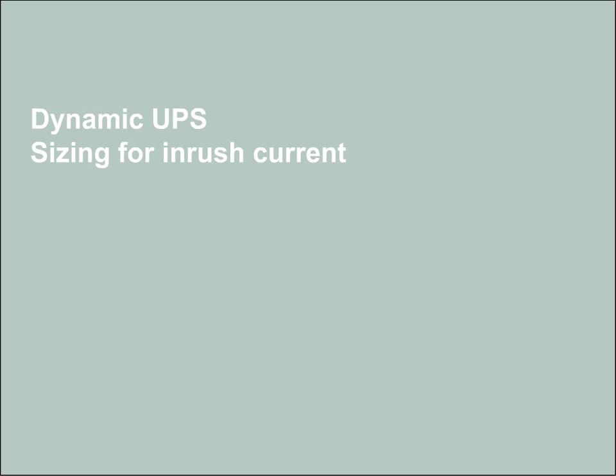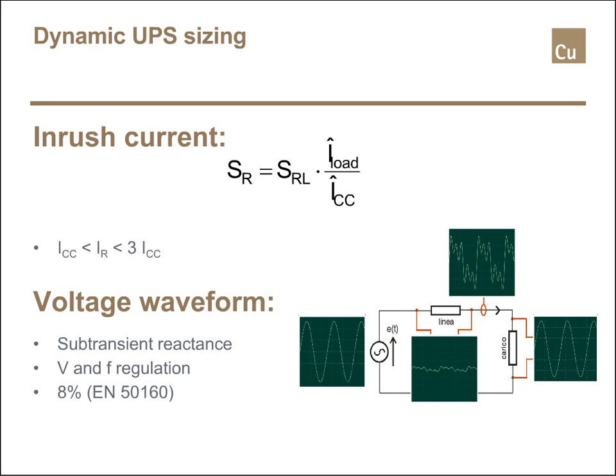Conclusion: pay attention to the inrush current, and if needed, increase the power of the UPS to be able to provide the requested inrush current. Now let's spend a few minutes on the same issue for dynamic UPS. More or less, the problem is still the same — loads require quite high inrush current, and the UPS is not able to provide any kind of transient current beyond its limits.